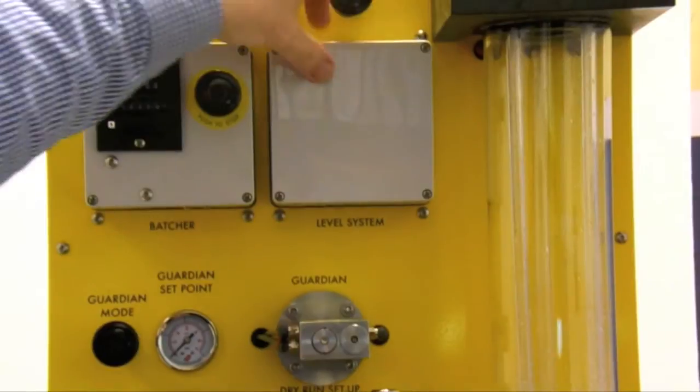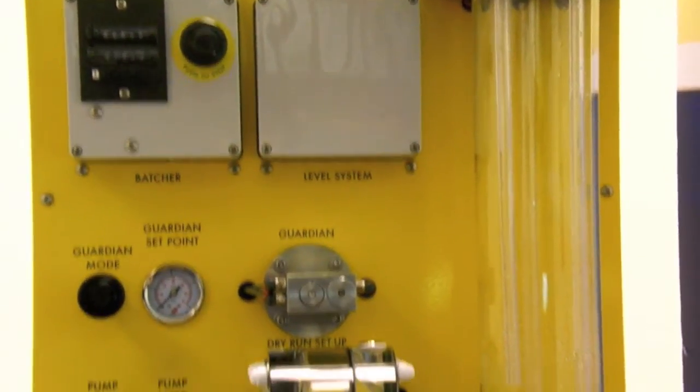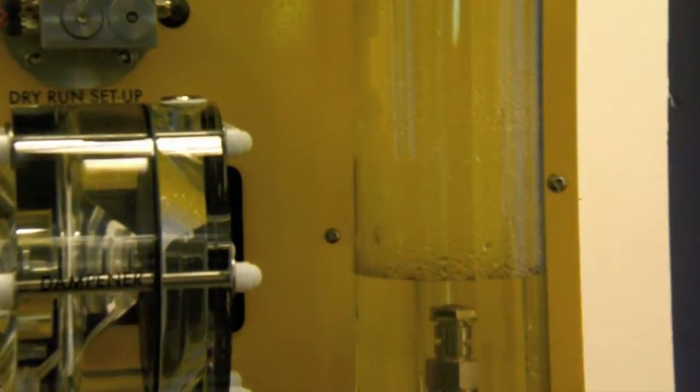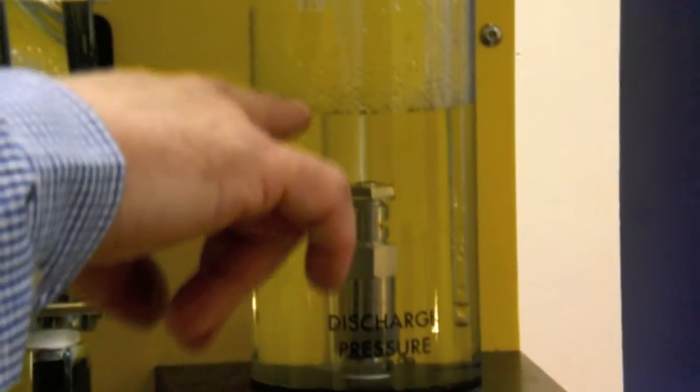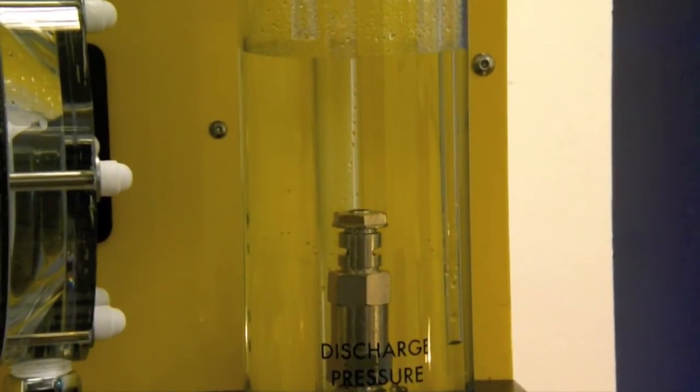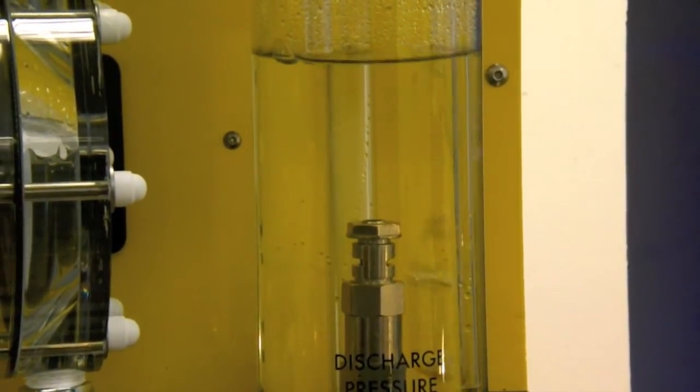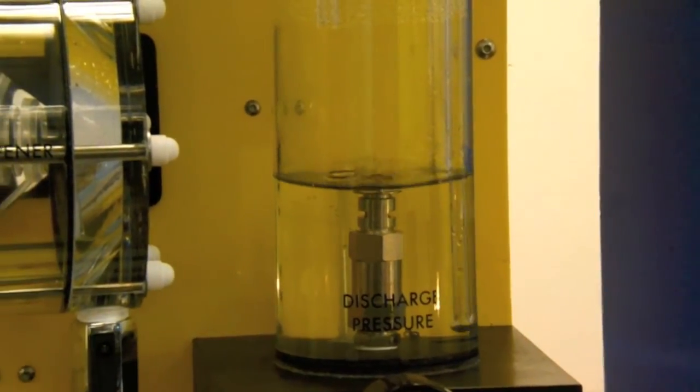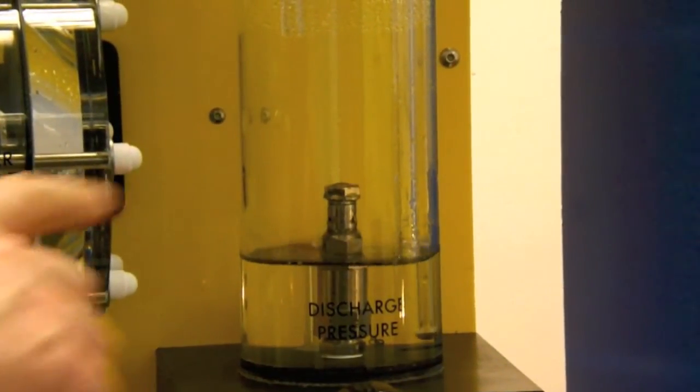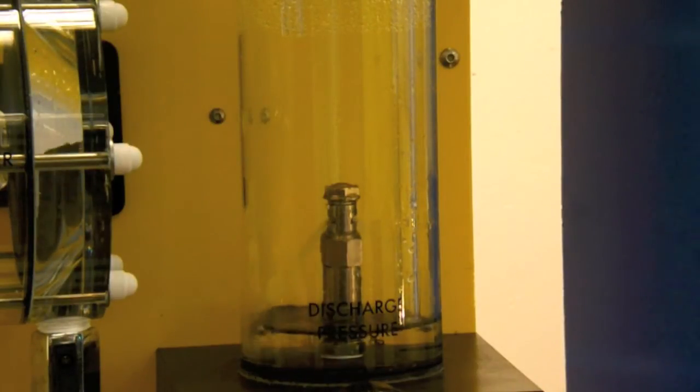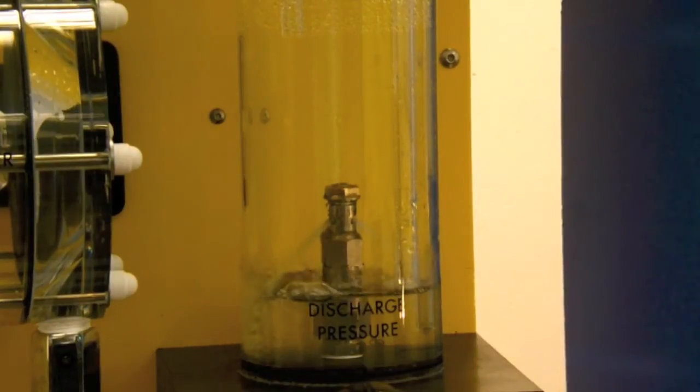The next system I am going to show you is our level control unit. Here the unit is programmed to fill the top tank here until it reaches our high level sensor. Once the liquid level reaches our high level sensor the pressure change in the tube will be picked up by our level control unit and it will shut the pump off. It is also programmed here to drain the top tank until it exposes our low level probe. And once our low level probe is exposed the pump will come back on and refill it up to the high level. So this system is very useful for maintaining levels in production tanks and production vessels.